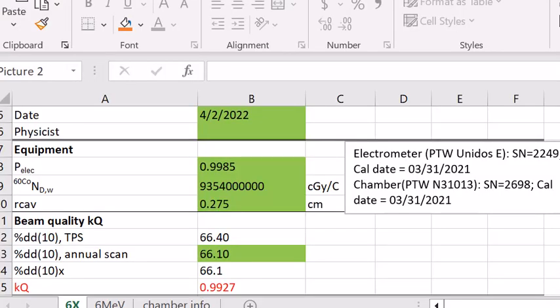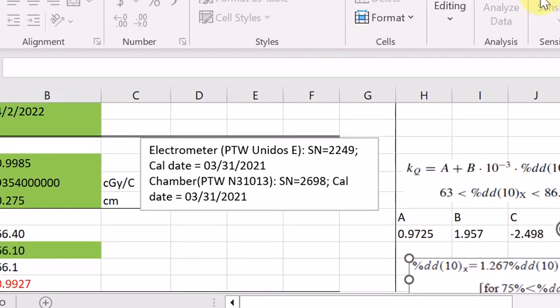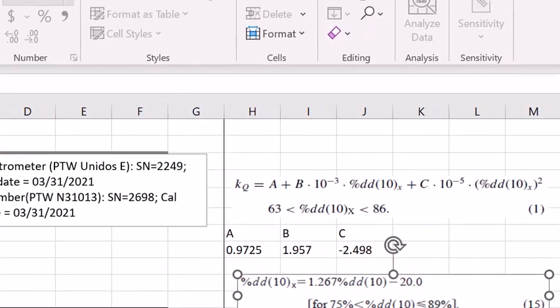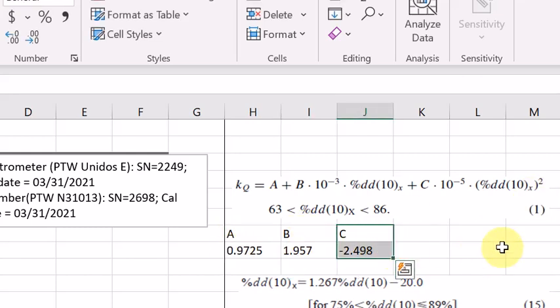In our TG51 annual, we actually use the addendum data. So this is actually the equation. Once we have the PDD at 10, we can use this equation instead of the tabulated data to obtain the KQ factor. The A, B, C values are from the TG51 addendum. So once we have the PDD at 10, we just plug into this equation using these three factors for A, B, C, and we can get our KQ value.